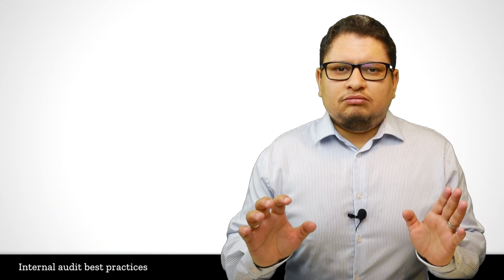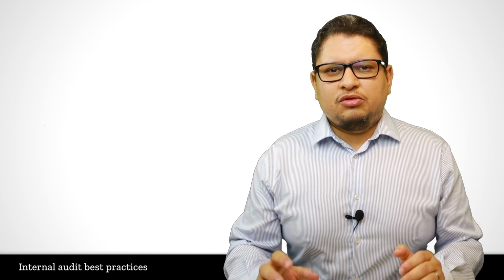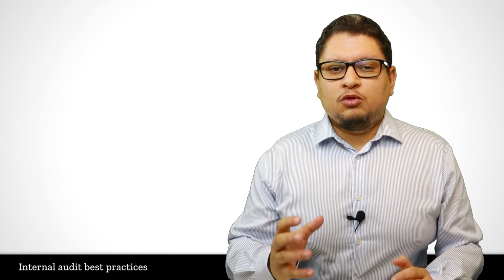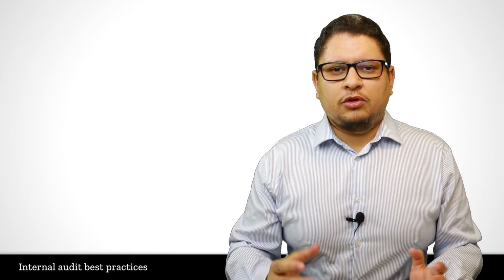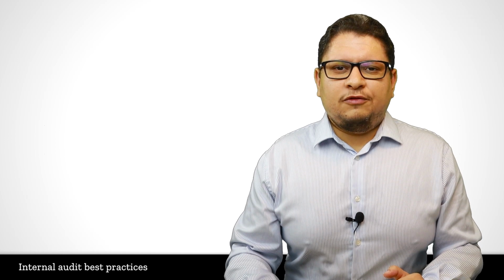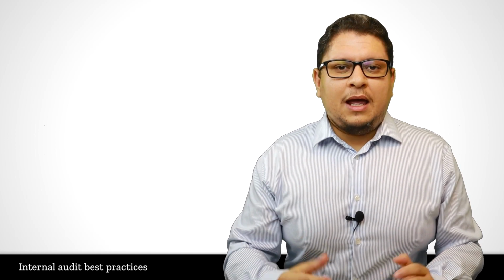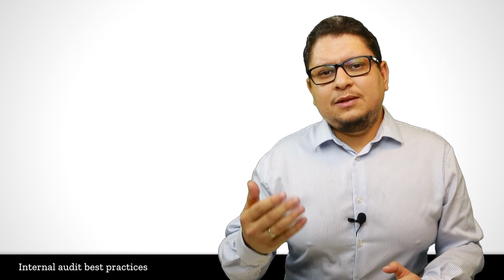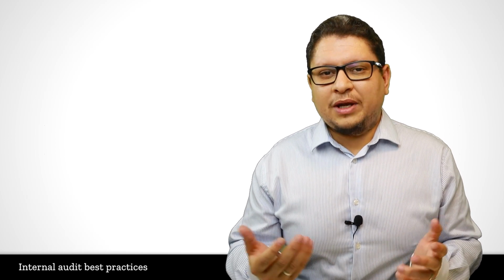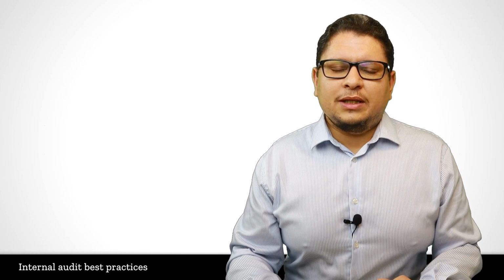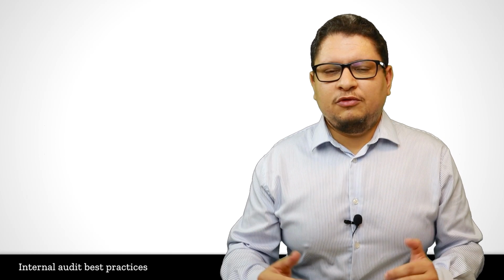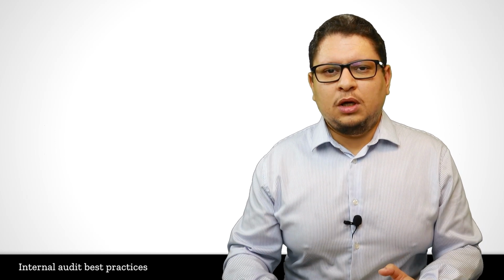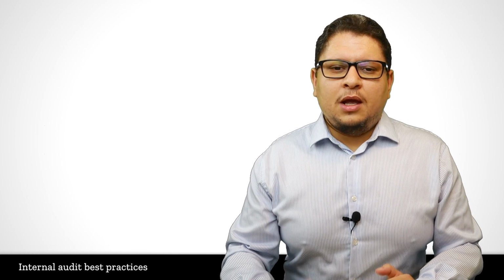Okay, so I think here I tried to explain to you quickly how to perform an internal audit. As I said, look at the ISO 13485 or the 21 CFR 820 for more details about what is expected, and use the ISO 19011 to see the methodology or guidelines to perform an internal audit, which can also be helpful because you can see what kind of template or document you have to build or create for that.